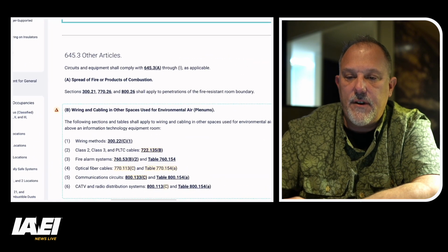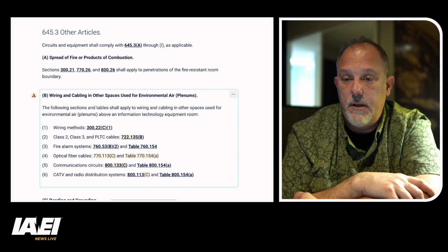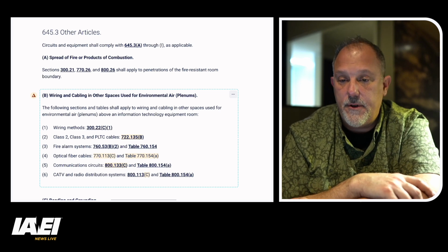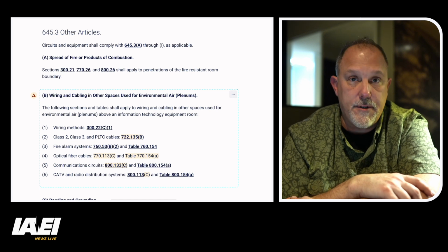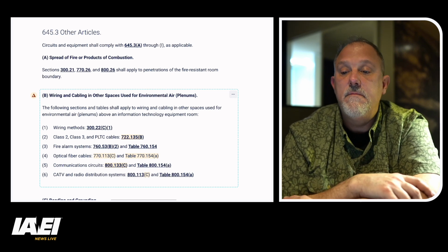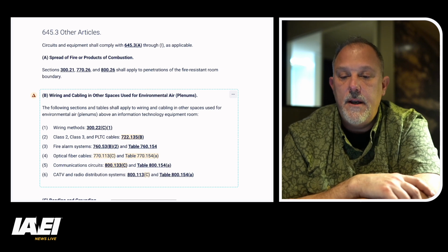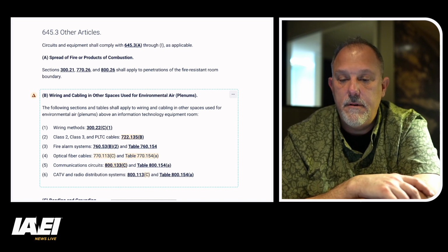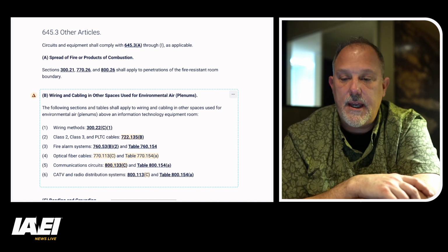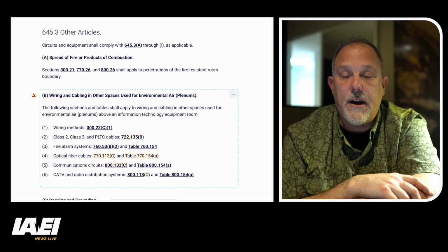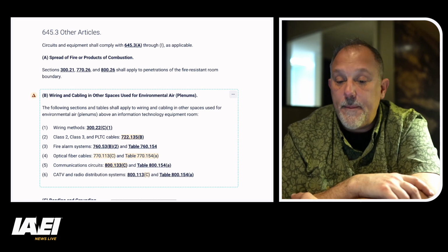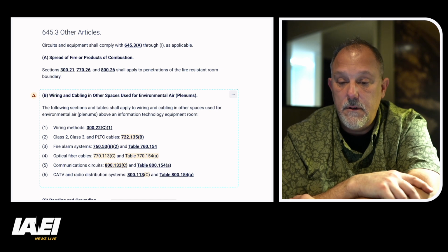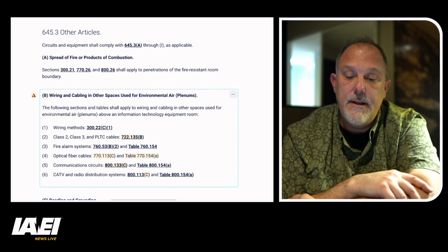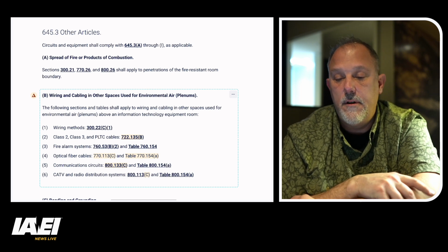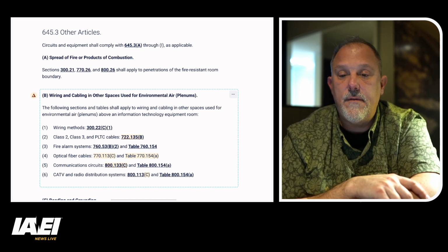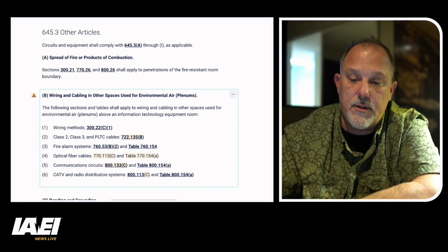Now, when you look at 645.3, when it talks about other articles, it points us to Article 300, 770, and 800 for fire-resistant room boundaries when you penetrate them. If you're looking at wiring methods, you're in Article 300. Class 2 and 3 and power-limited tray cable in 722. Fire alarm systems in 760. Optical fiber cables in 770. Communication circuits in Article 800. And then CATV and radio in 800. So it gives you the pointers to those other articles and sections specifically.